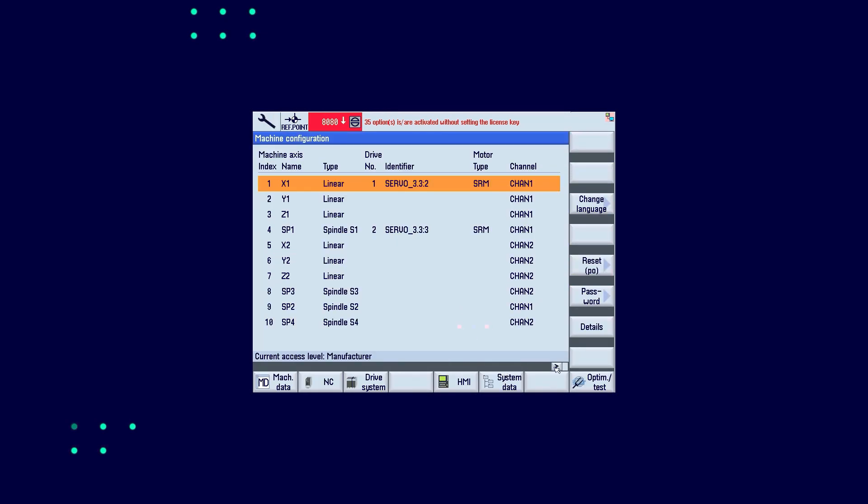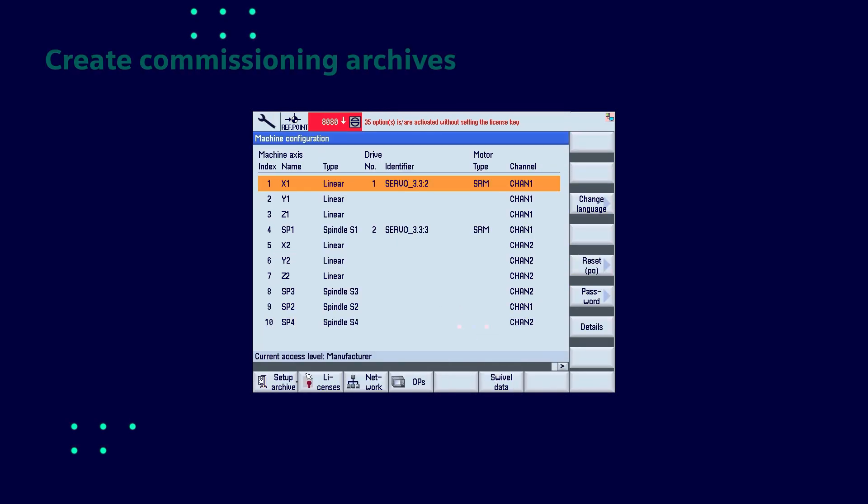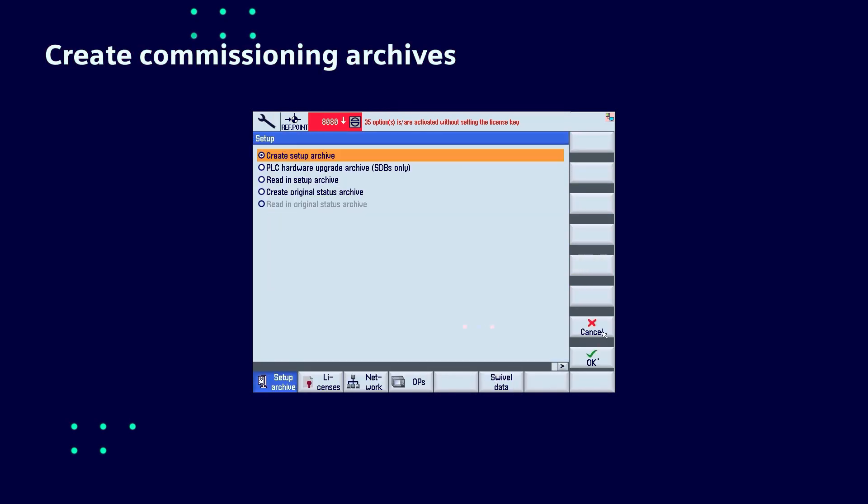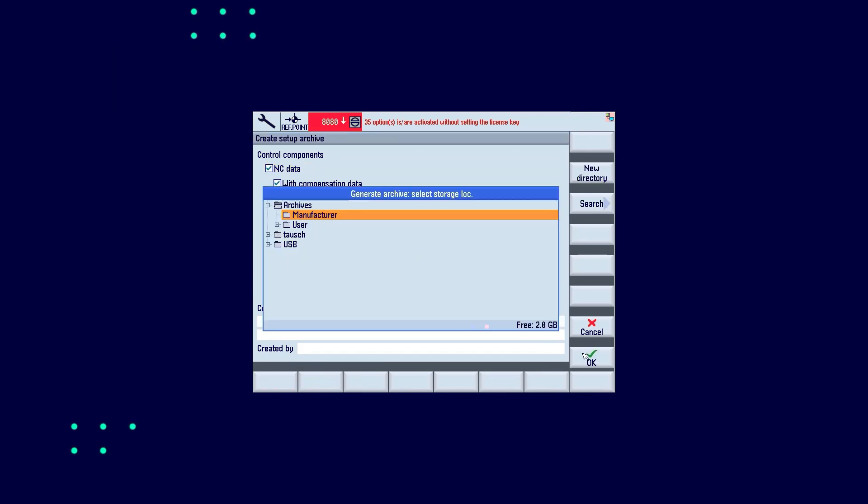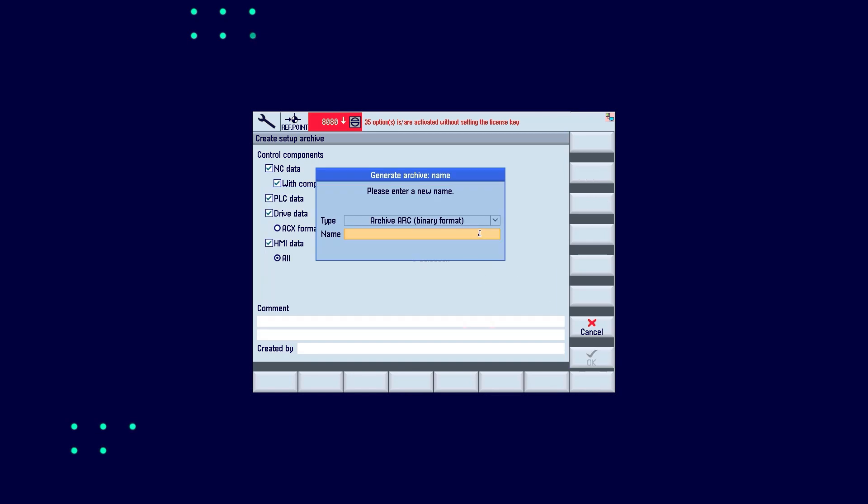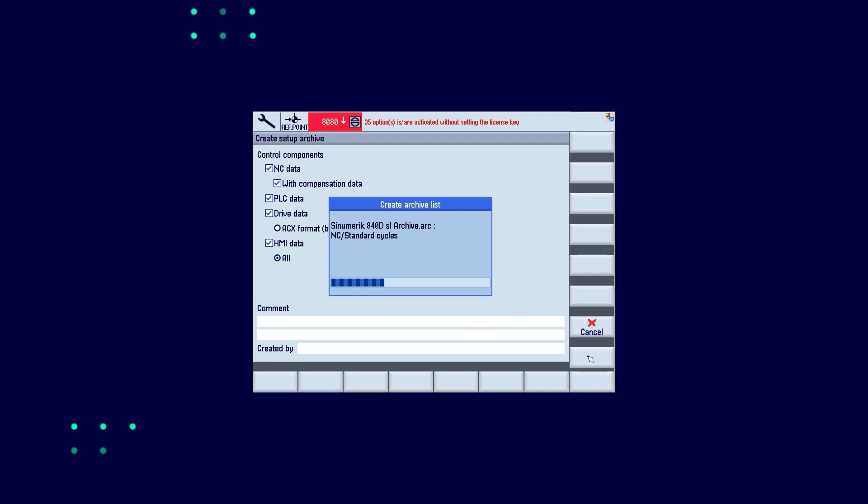You should first create a backup of your machine control, the so-called commissioning archive. Here we create this backup via the HMI of a Sinumerik machine. This works similarly for all Sinumerik controls. Once the archive has been created, the BFC client software can be installed on the controller.